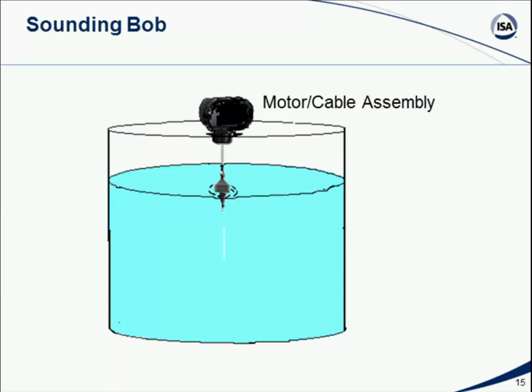Basically, where the bob hits the surface and where the weight that we're feeling from the motor cable assembly changes, at that point we know that the bob has reached the surface. And if the motor assembly is encoded in such a way that it can keep track of how much line has been let out, then ostensibly we have a measurement of the distance from the motor assembly down to where the surface of the fluid in the tank is. So of course, if we know how tall the tank is, we can subtract that from the top and end up with what the vertical distance in the tank is. And a motor cable bob assembly like this is something that's been used for years in the process industry to take an occasional automated measurement.